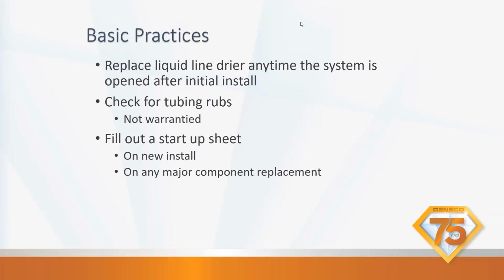You're supposed to check for tubing rubs on the equipment. Open up the side doors, check the tubing rubs on all the cap tubes, make sure that they are not rubbing against each other. Okay, they've done a whole bunch of different things at the factory. They go through before they send it out. On the line, the last person puts their finger in between all of the tubing to make sure that they're not touching.